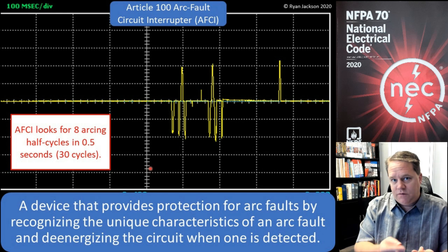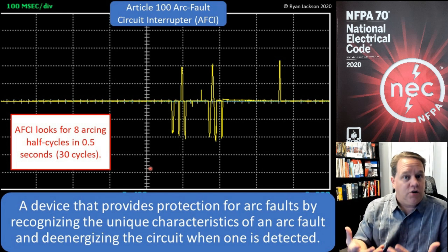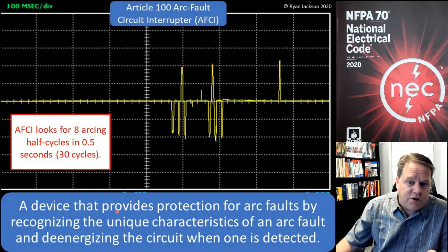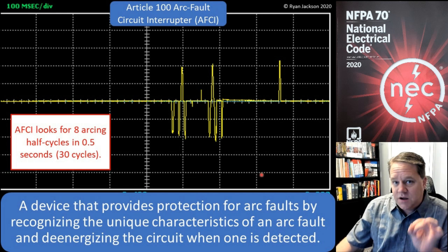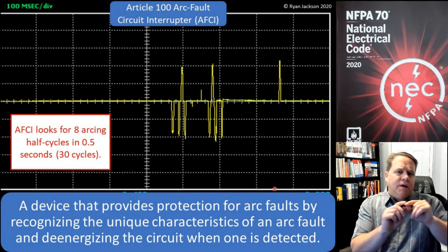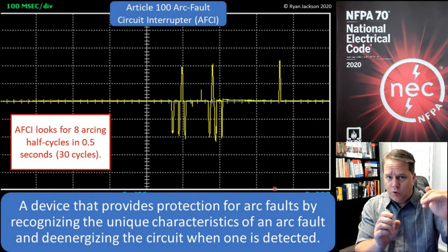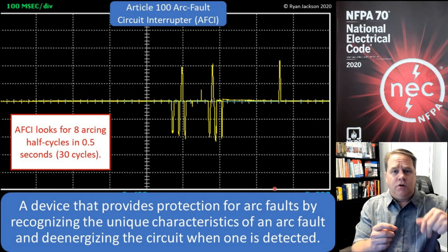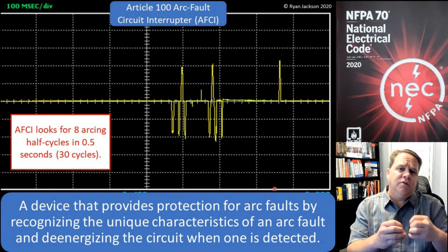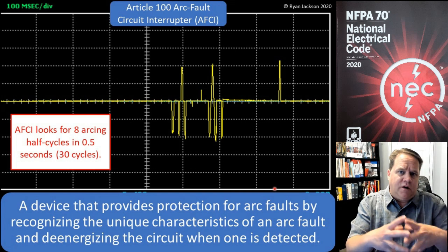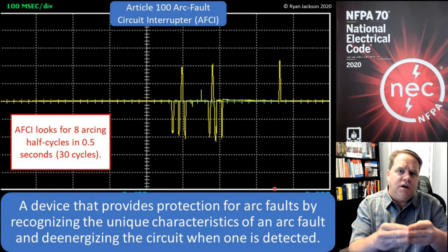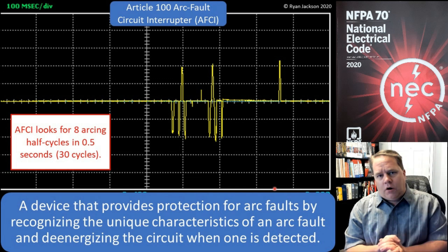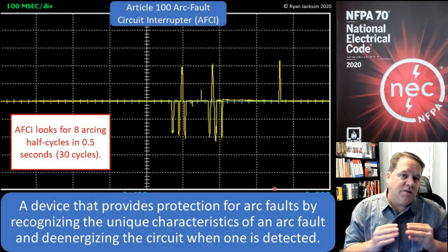An arcing fault looks like this photograph here. The unique characteristic is that the waveform will peak and then go flat, and we call that shouldering. So it'll peak, it'll shoulder, it'll peak, it'll shoulder — it's an intermittent thing. It's arcing several times, and that's what creates the hazard. Not every arc is necessarily a hazard, and that's where this gets really tricky.